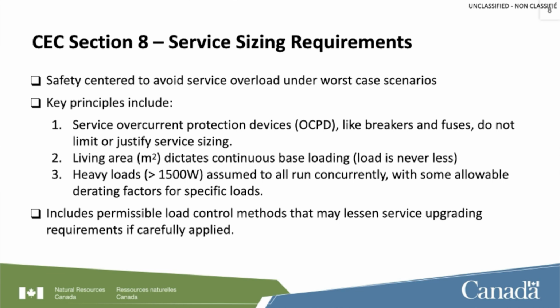But the service overcurrent protection devices, like your master breaker, you cannot just have a 100 amp master breaker that trips once you hit 100 amps. That doesn't mean you can put 150 amps of service behind it. The code will not let you do that.